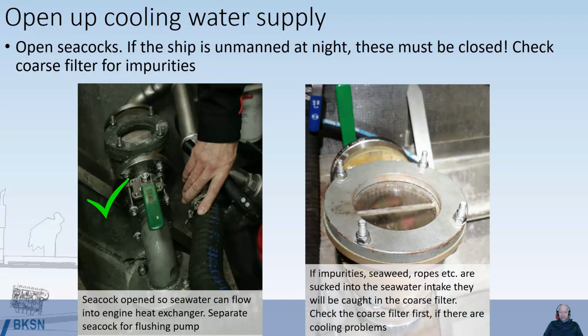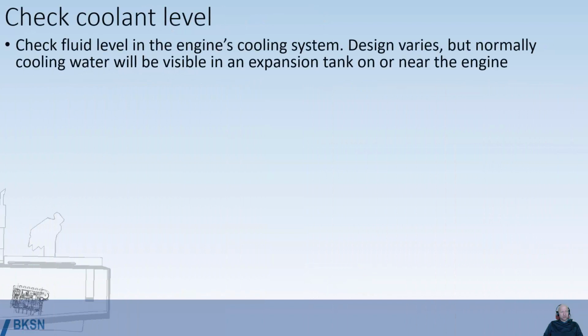Okay, open that one. Check the coarse filter. If there's any impurities, seaweed, ropes that are sucked into it, may clog the coarse filter. Check it first. That's the first thing you check if you have problems with cooling. Okay, so that's checked. Next is to check the coolant level in the engine's cooling system.